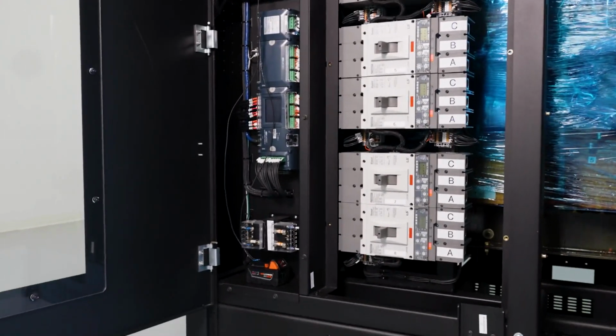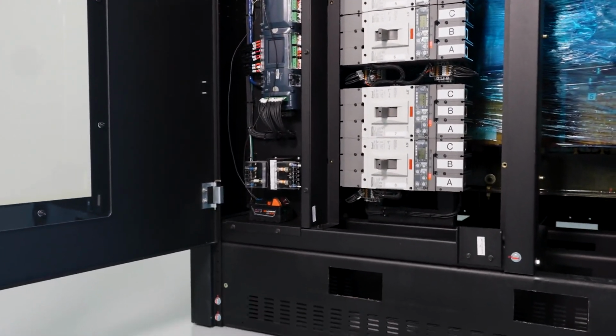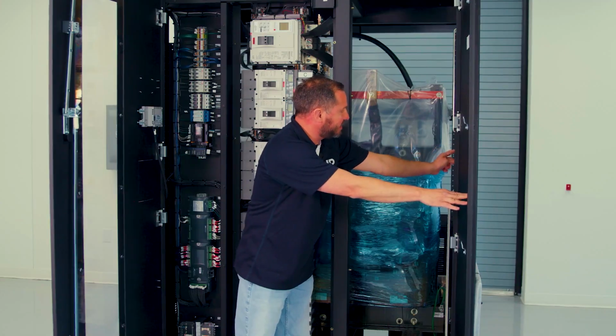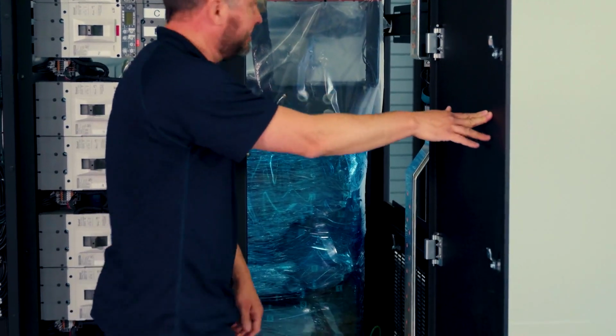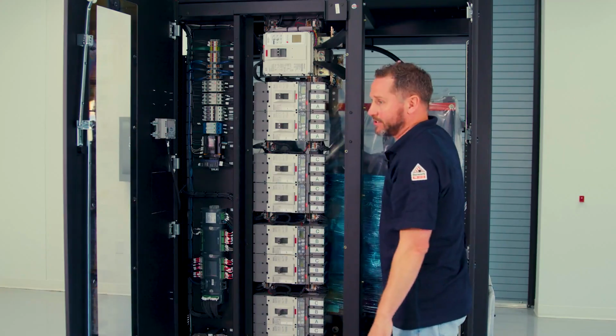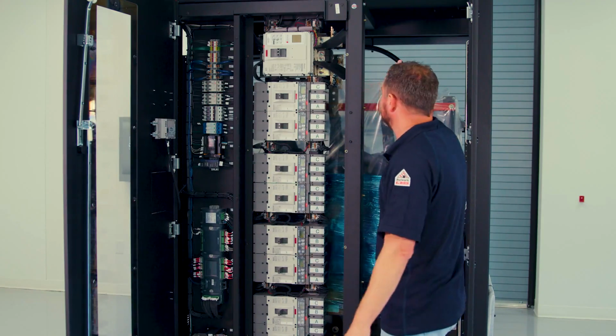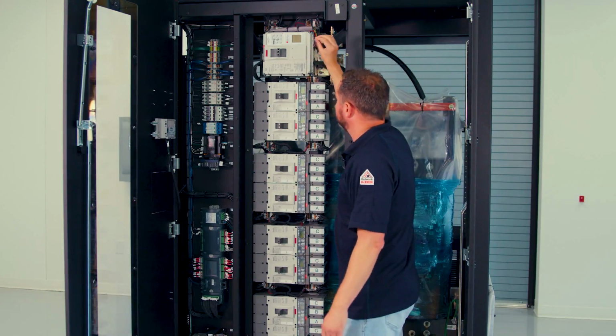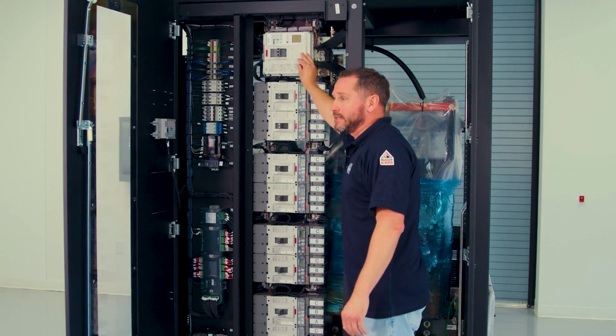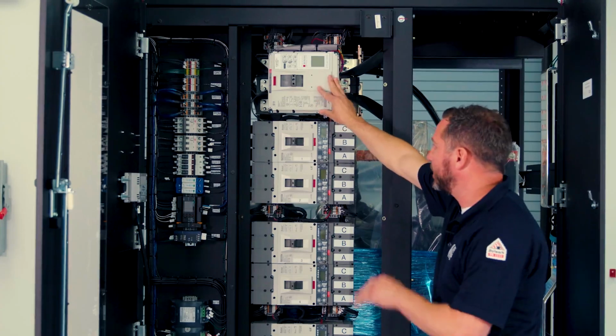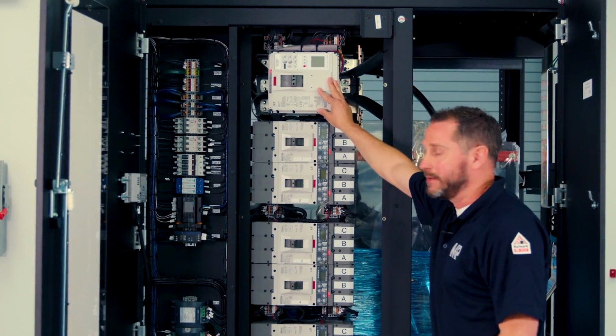We do have our neutral CT in the very, very back bottom back there, and our ground CT here is at 100 amp. That's going to be 800 amp CT, as well as our primary and secondary side of this transformer is also going to be 800 amp CTs. Because we're tapped at 415, we're set at 696 amps capacity on our main breaker. So that is why we're at 600 amp trip.